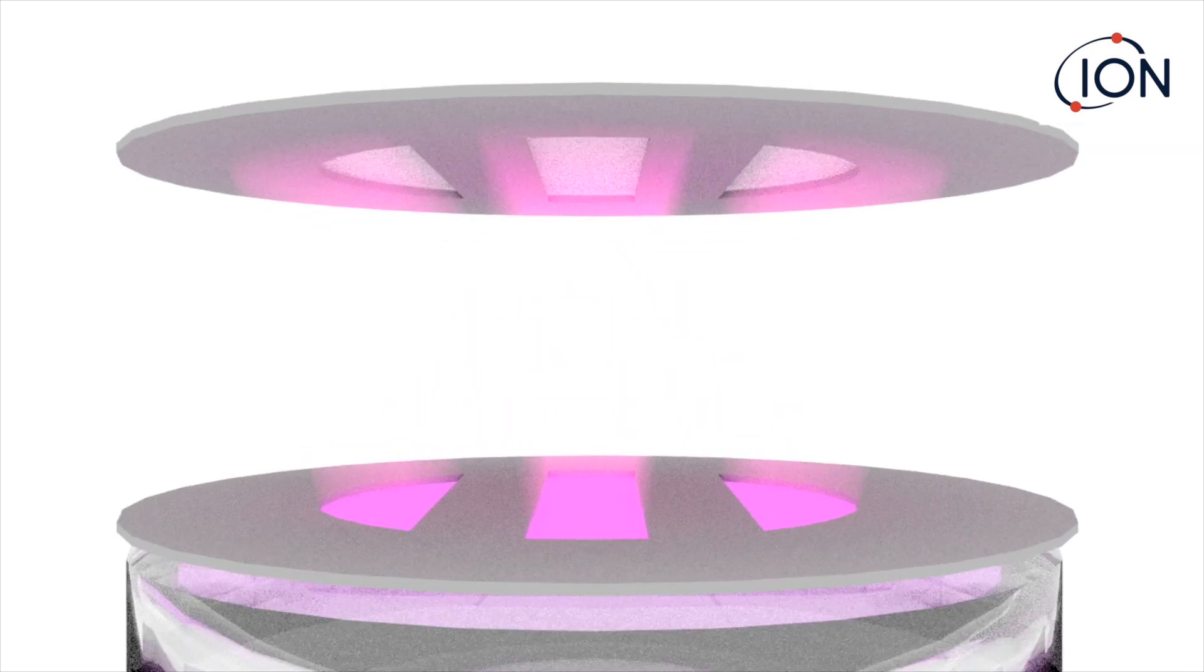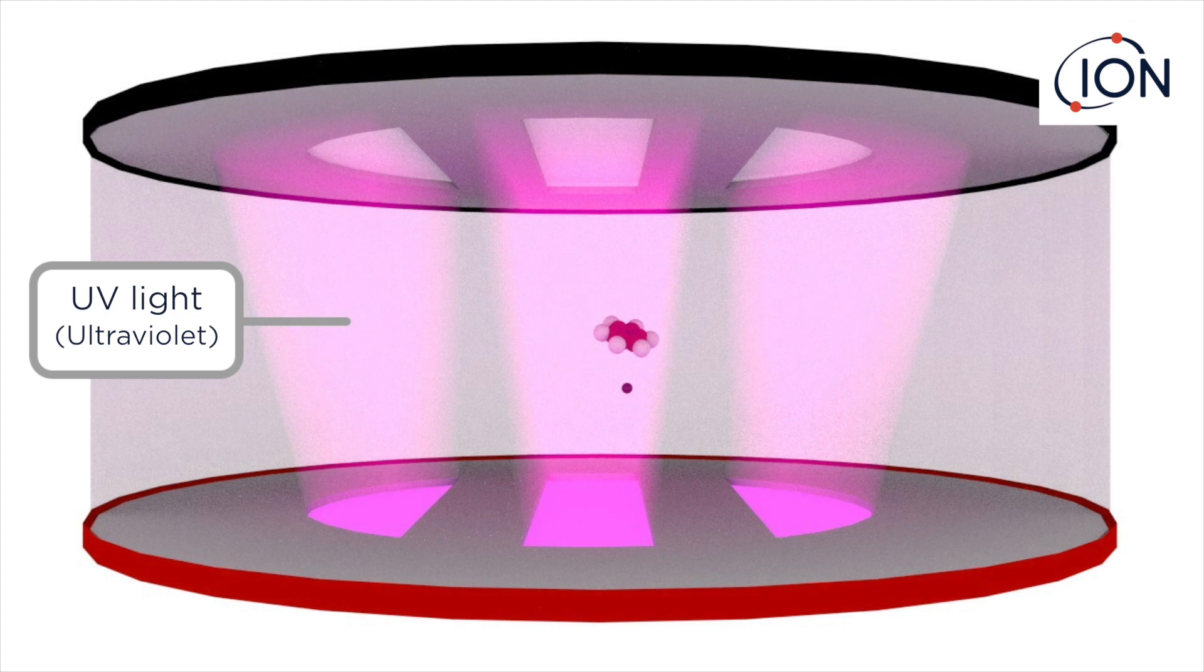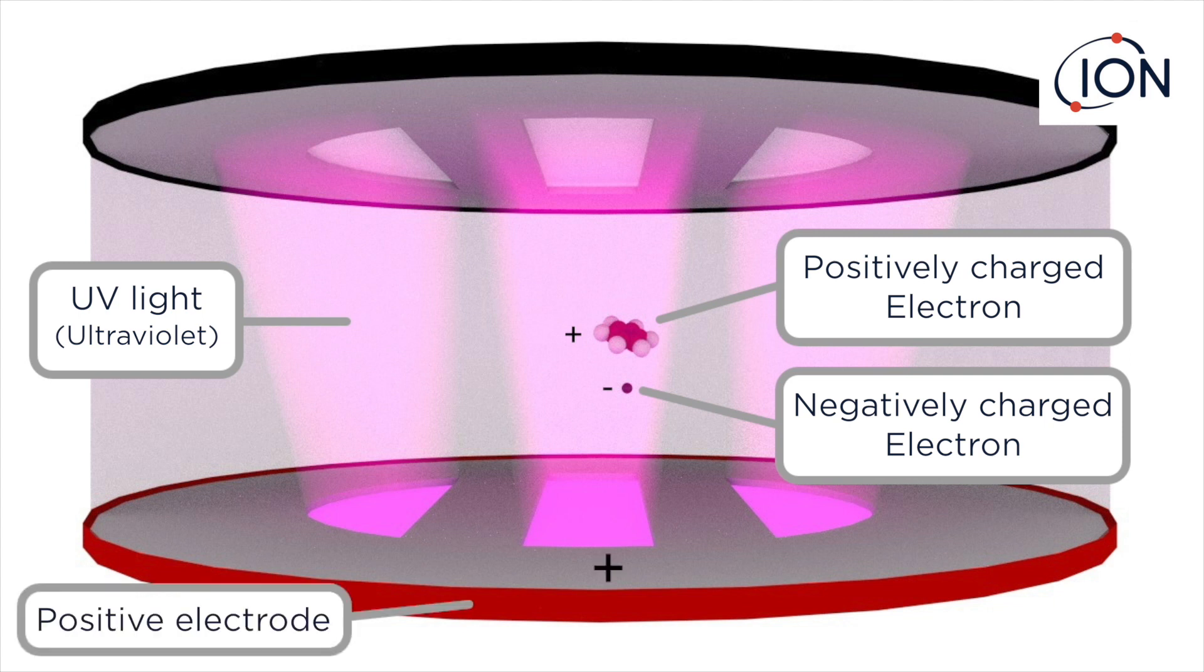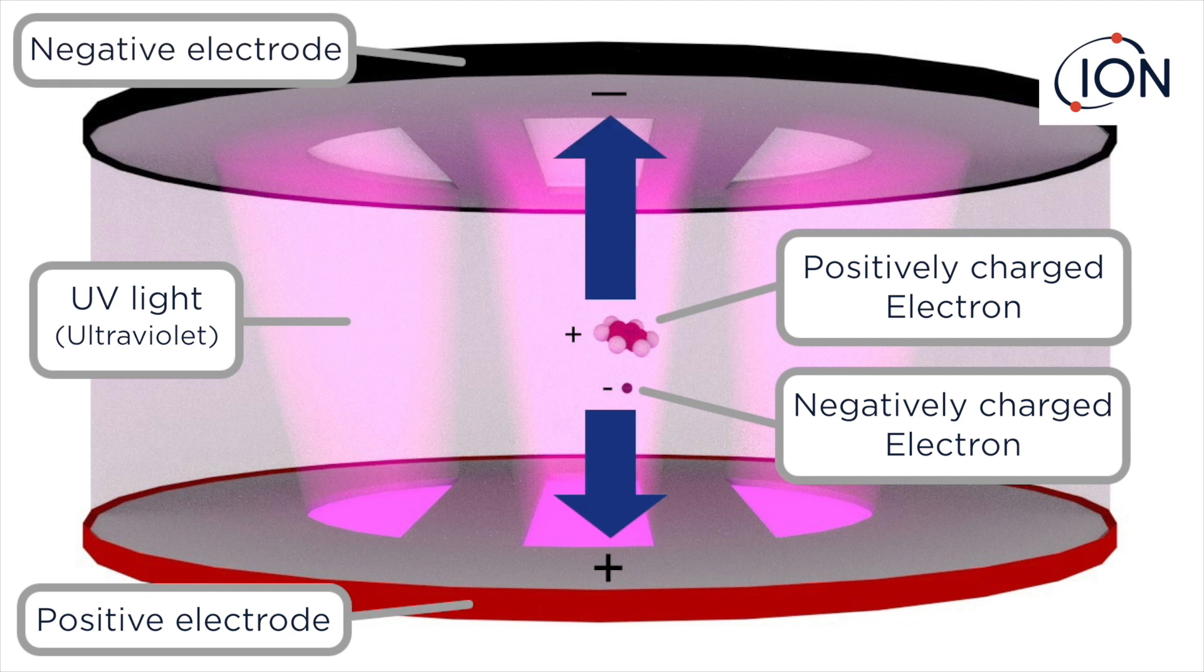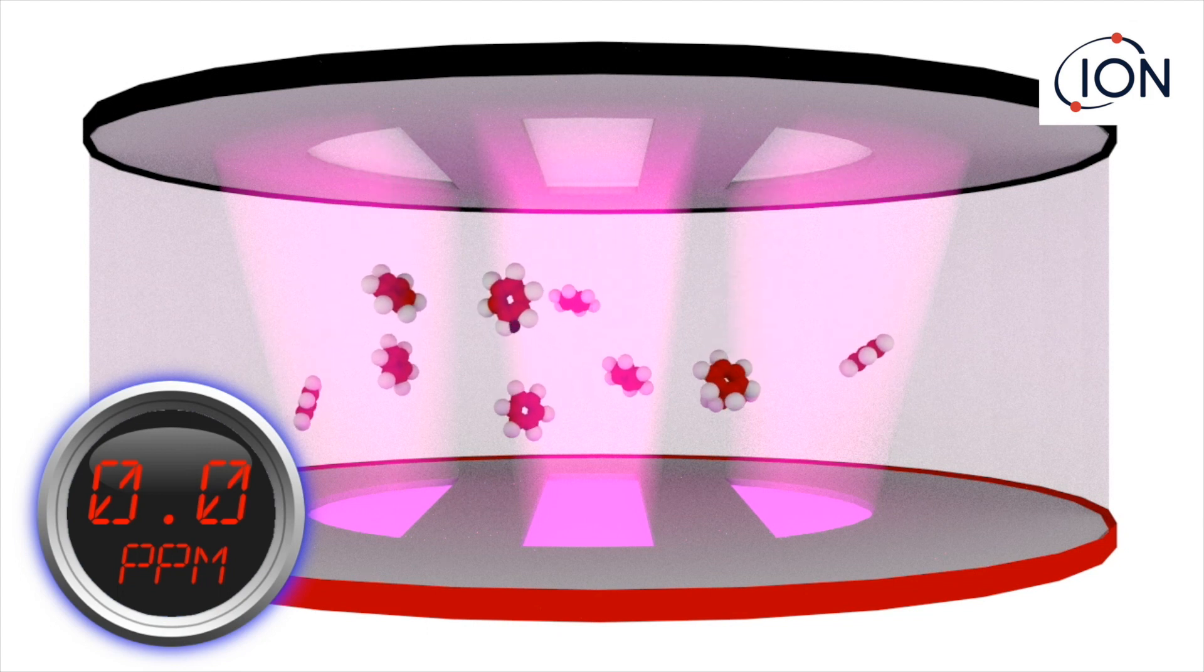When VOC gas enters the detection chamber, ultraviolet light energizes the molecules, releasing negatively charged electrons. The VOC molecules therefore become positively charged. The negatively charged electrons are attracted to the positive electrode, while the positively charged molecules are attracted to the negative electrode. This results in the generation of a tiny electrical current that increases with gas concentration.